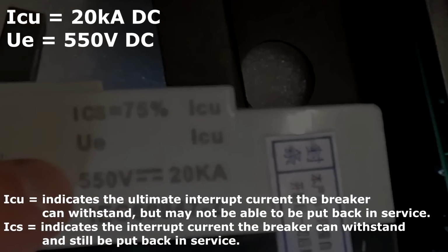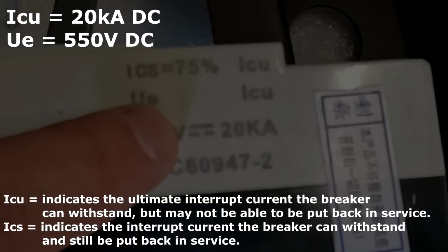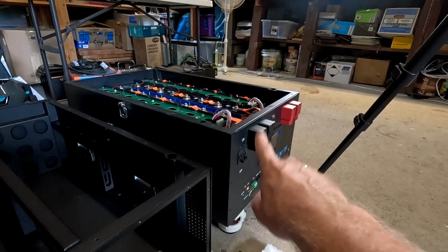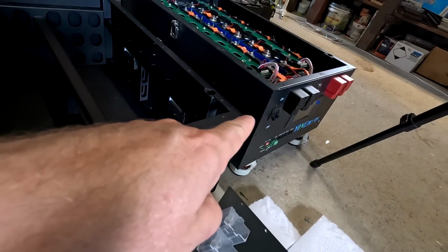While we got this breaker out, we can also see the specifications. It's 550 volts DC and 20 kiloamp of breaking capacity. So this breaker is a huge improvement from the breaker they used in the old battery box. That is a breaker, this one is a toy.